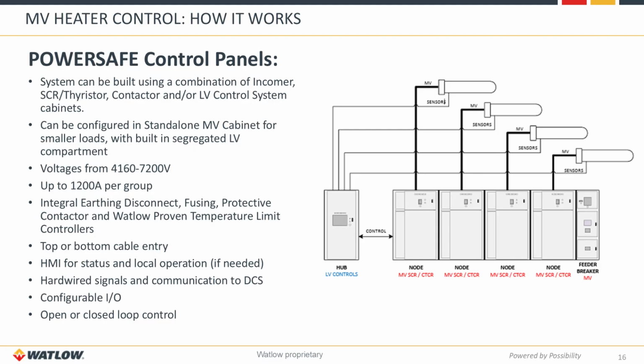So as I stated, the system can be built using a combination of these incomers, SCR thyristor cabinets, contactor cabinets, and low voltage control cabinets. It can be a standalone unit, or if you've got a larger system, they can be stacked together and used as a bundle within groups. Our voltages do range from 4160 up to 7200 on this, and you can have up to 1200 amps per group.